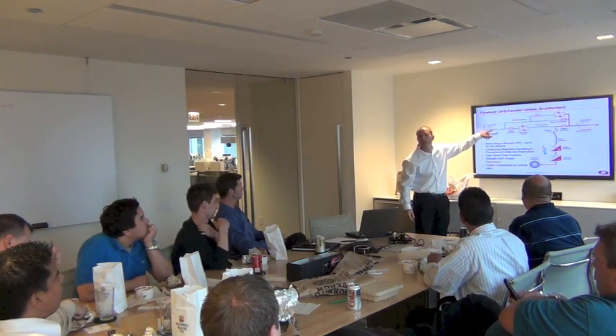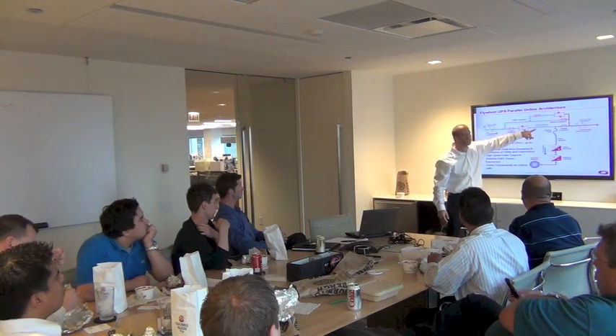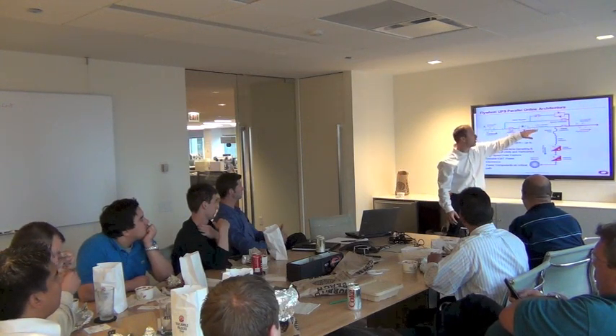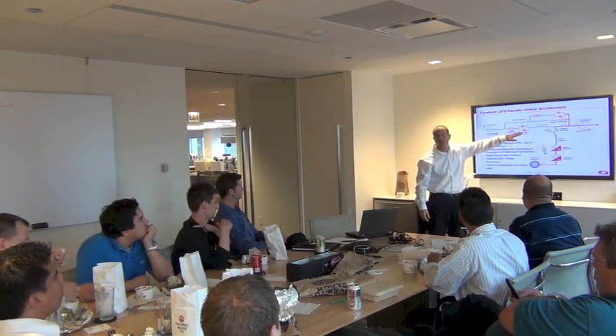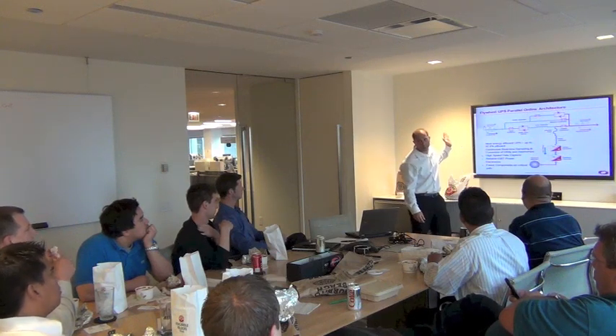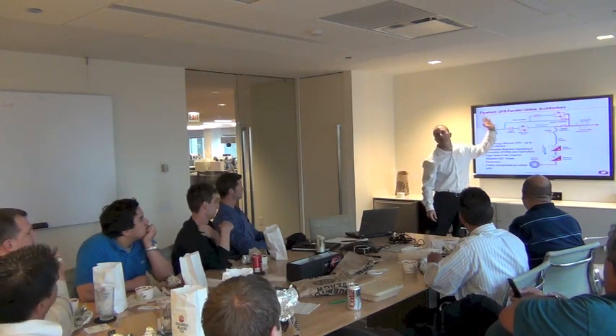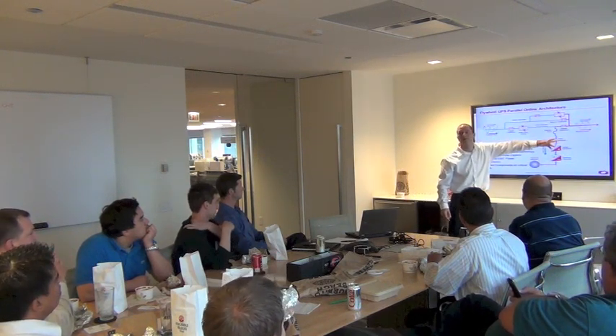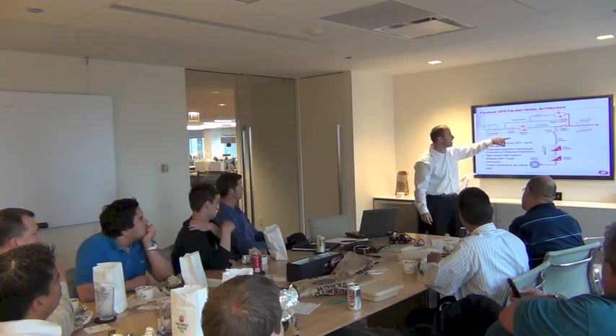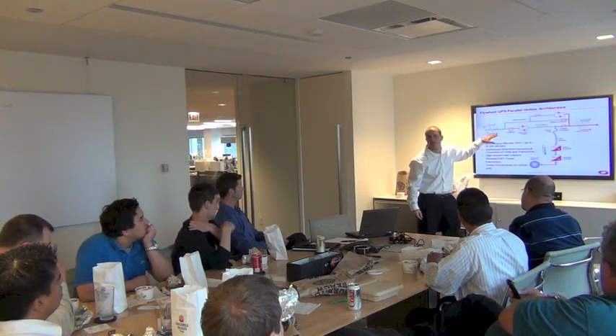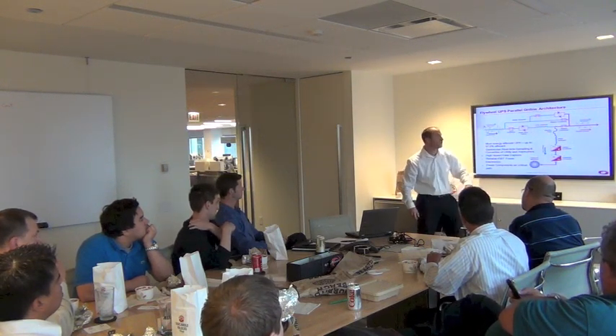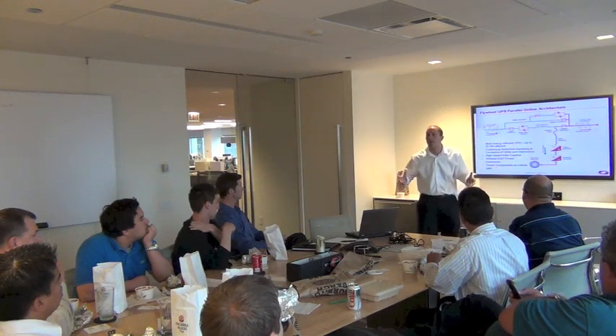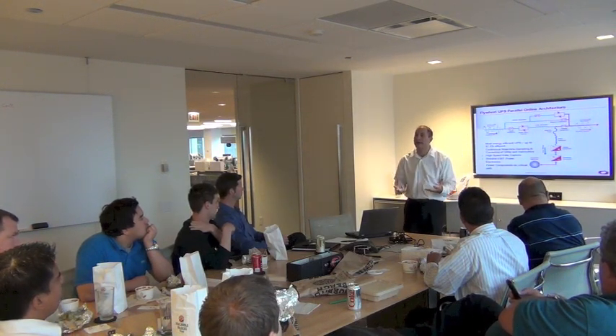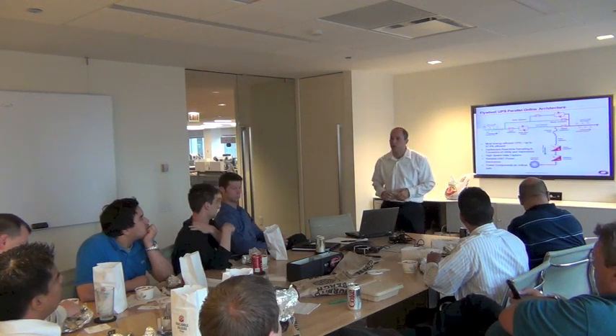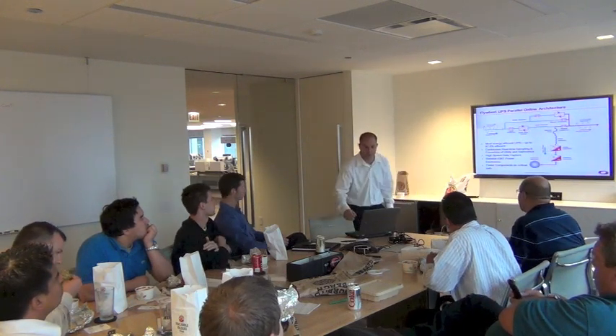Also, utilities are a very stiff source. Even though we have a very large choke in the middle, on our mains in each flywheel cabinet, which basically prevents any harmonic voltages from propagating from the input to the output, as well as harmonic currents from propagating from the output to the input, it's also a stiffer source. So when X-rays fire, your inverter's not seeing the entire bulk power. That's why we have good overload capability as well, and it gives us a little more flexibility with sizing when we're dealing with imaging equipment.